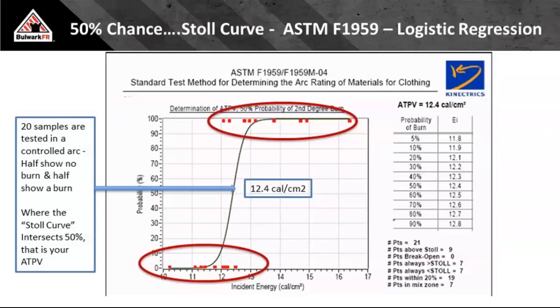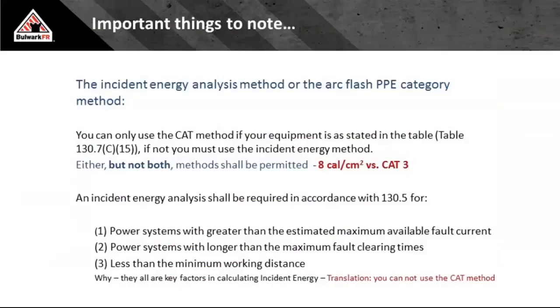So what's an ARC rating? A 50% chance of a second degree burn. In order to find out what that is, I have 10 that pass and 10 that fail, and my 50% probability is based on the Stoll curve being applied to the results. Once I know that, I communicate that on my shirt, pant, coverall, or ARC flash suit. I tell you what the ATPV or the E sub BT is, and then you're going to match that PPE to your incident energy. And remember, we're going to do that either by the incident energy method or by the CAT method. Remember these numbers, 8 cal and CAT 3, and we'll talk about those shortly.